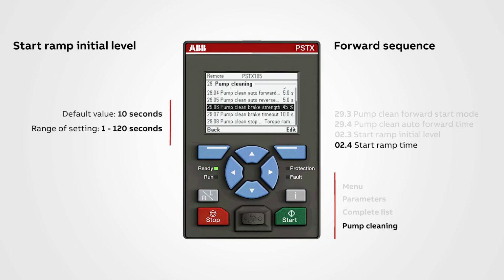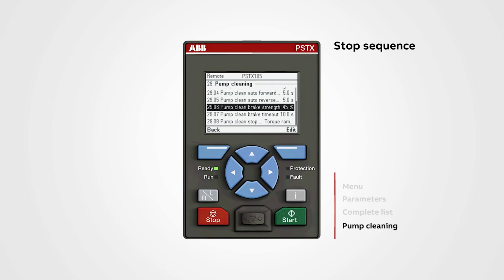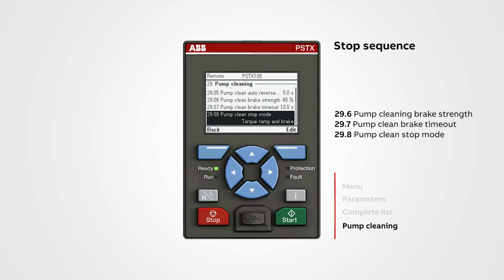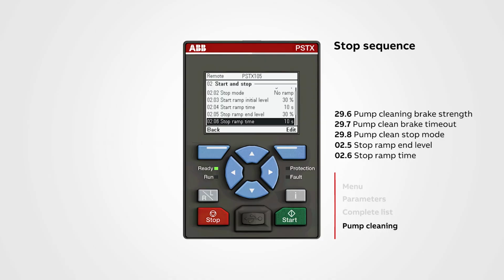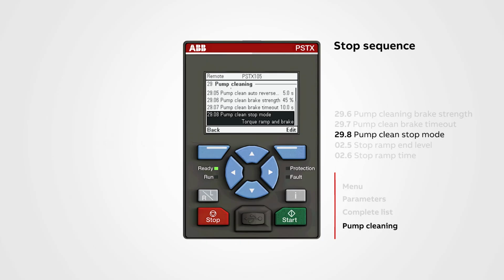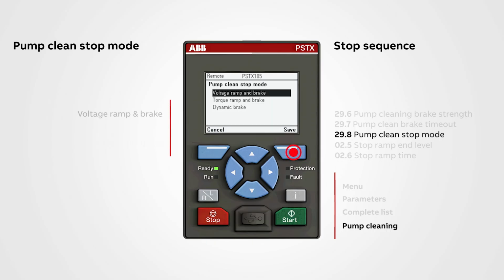Now let us jump back to pump section 29 again and look at the last part in the sequence. Okay, let us dive into the last part of the sequence, where we have 3 parameters to set: 29.6, 29.7, and 29.8, which relate to how the pump should be stopped, and parameters 02.5 and 02.6, which relate to voltage and torque stop ramp. We start with the parameter 29.8, pump clean stop mode. This will set the stop mode that we should use after the pump cleaning forward has finished. We have 3 selections to choose from. The first one is the voltage ramp and brake. The second option is the torque ramp and brake. And the last one is the dynamic brake.